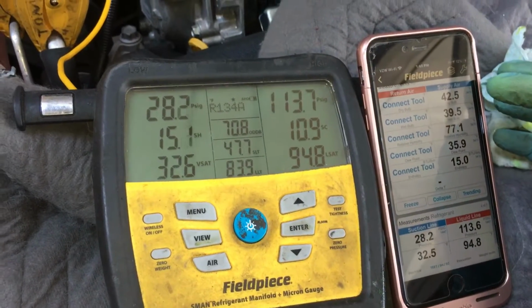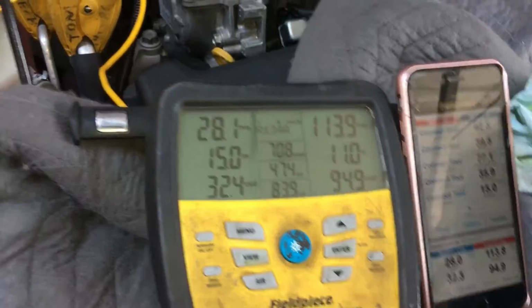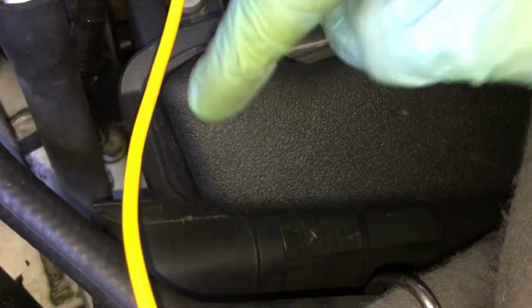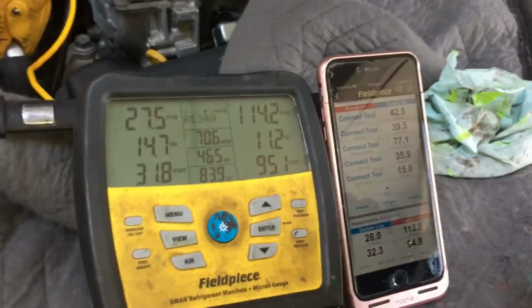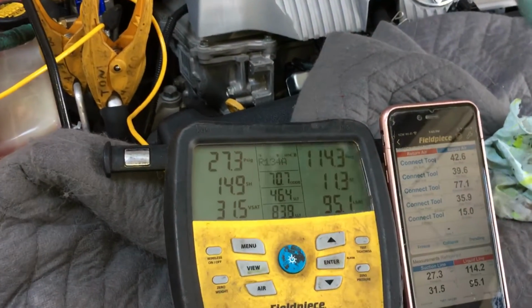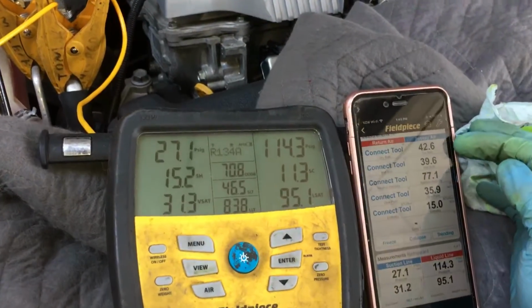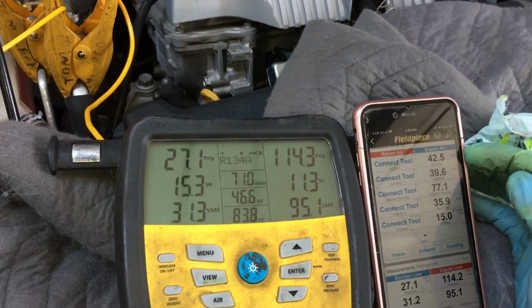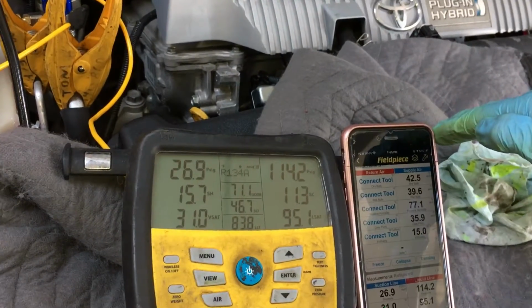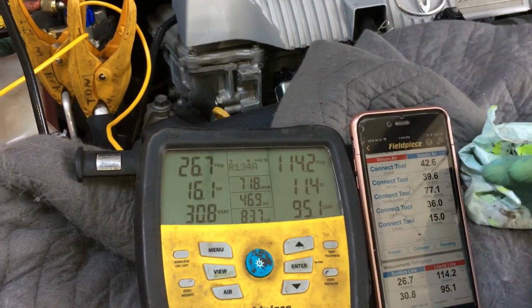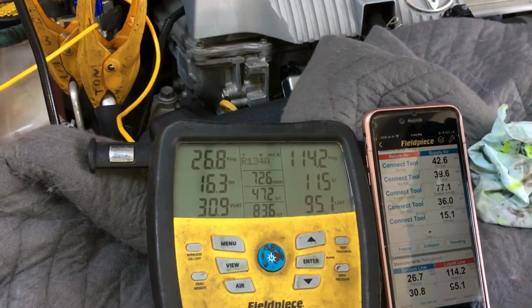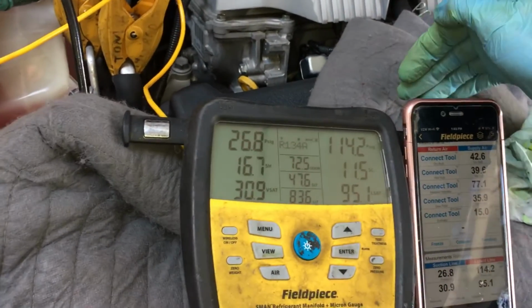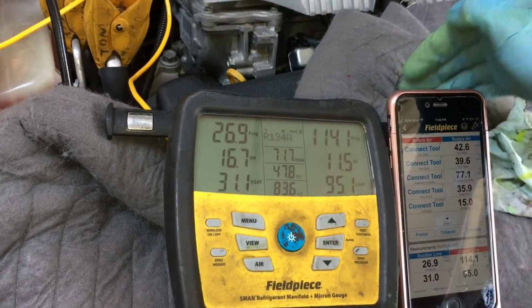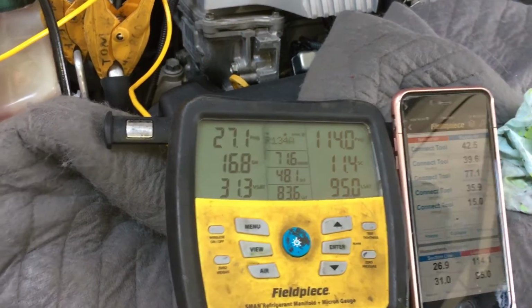And the reason it has risen, it's not working hard. You don't hear the compressor winding out now. It's running, but it's not winding out because it's at near set point. So it doesn't need such a cold air supply to try to achieve set point. So it has lessened off its potential. It doesn't need to wind out the compressor anymore, so it's not working hard anymore.